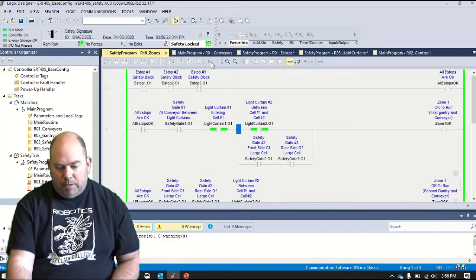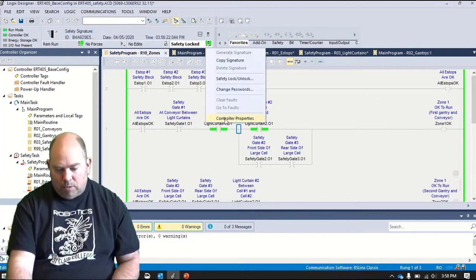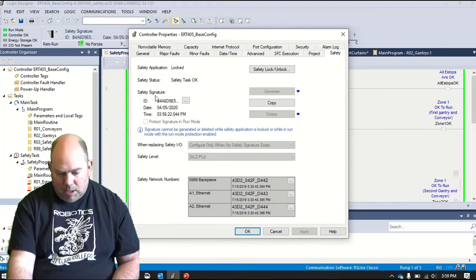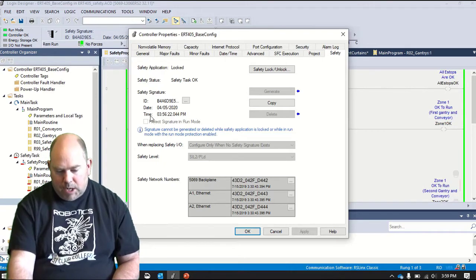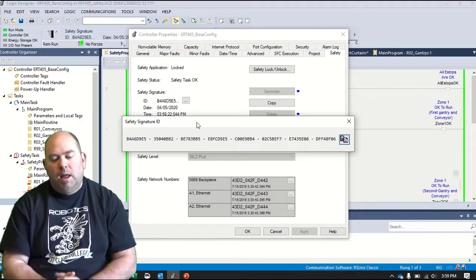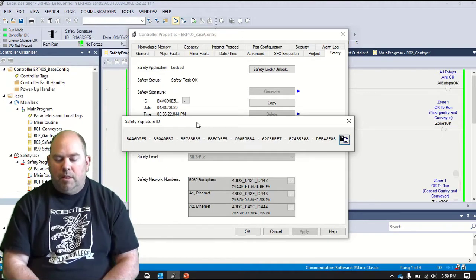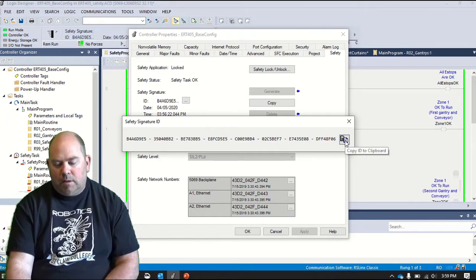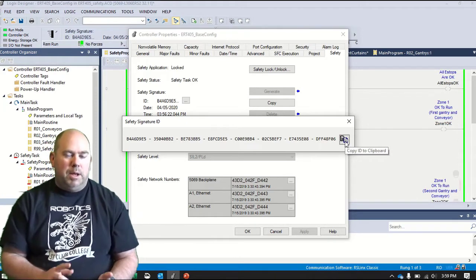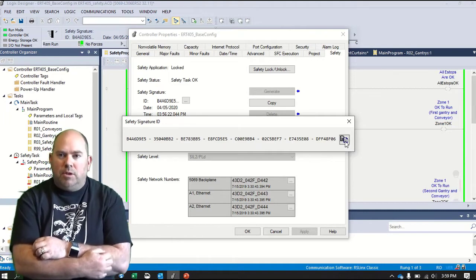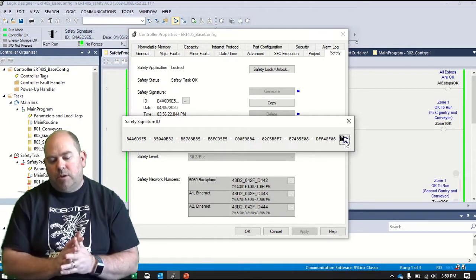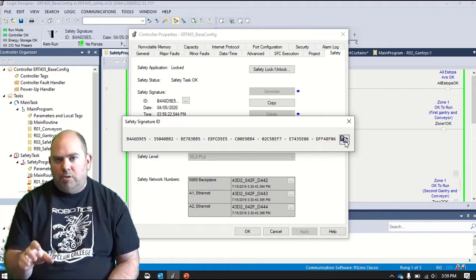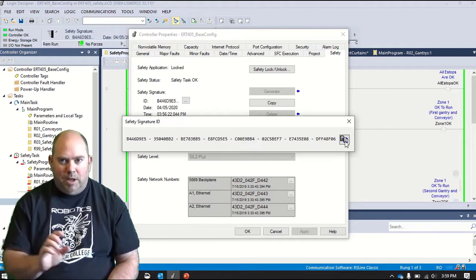Now if I want to look here, if I go to controller properties, under safety, you'll see safety signature right here. This has a time, so that's a time and date stamp. And then this big long code here, that is the actual safety signature that has been generated. You can copy that, copy it to your clipboard or whatever, write it down, paste it wherever you want, put it in an email. Whatever it is, but that is the unique signature to at the time when you locked this. So that is your verification that this is the way the system was at the time when I was finished with it and left you with it.